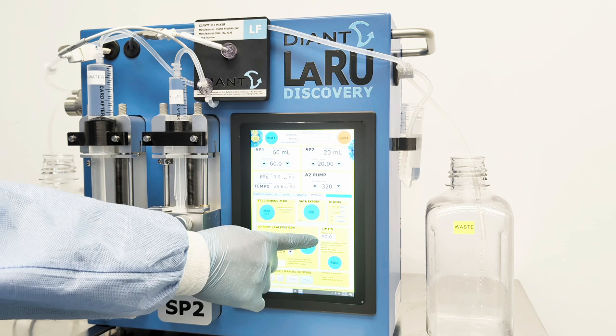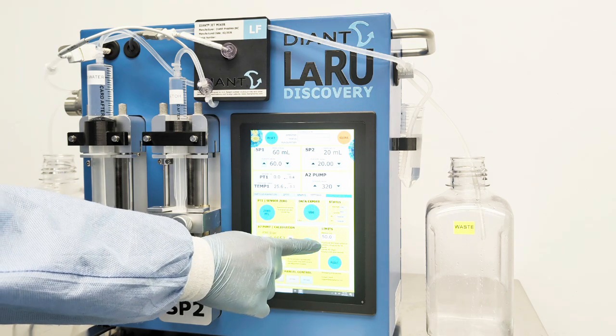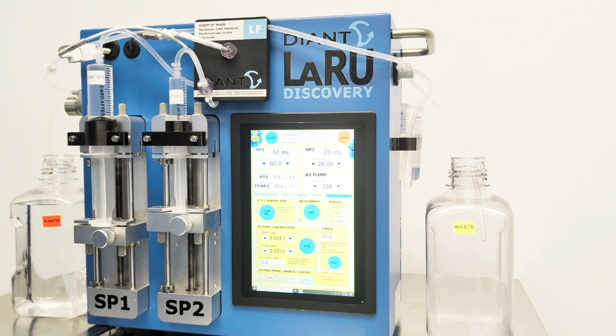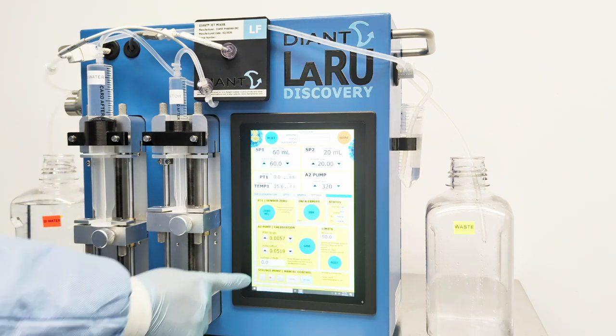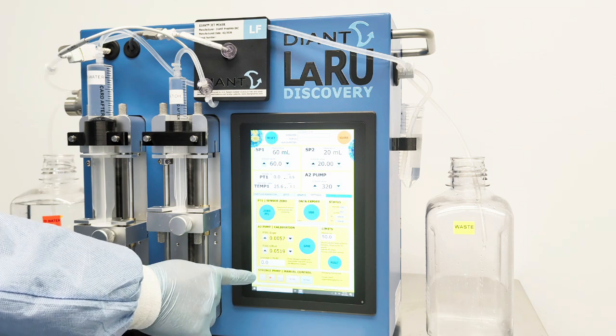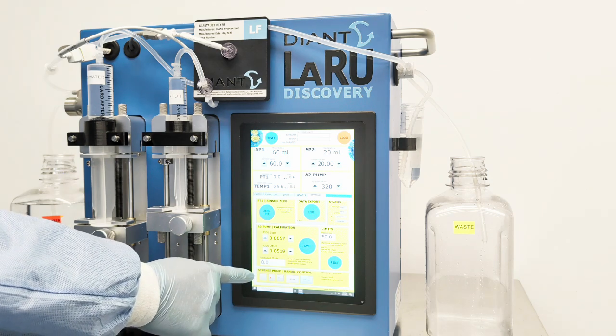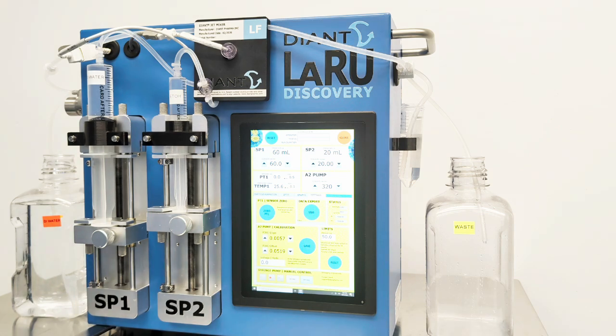Pressure limits. There's one pressure limit on the system, currently set to 50 psi. This can be adjusted. If you do hit the 50 psi limit, the system will stop. This is to protect the pumps and protect the various components on the system. And then you have to come to the settings screen and click the reset button in order to run the system again. On the bottom, there is a syringe pump and manual control, and this is typically only used for debugging and diagnostic purposes.